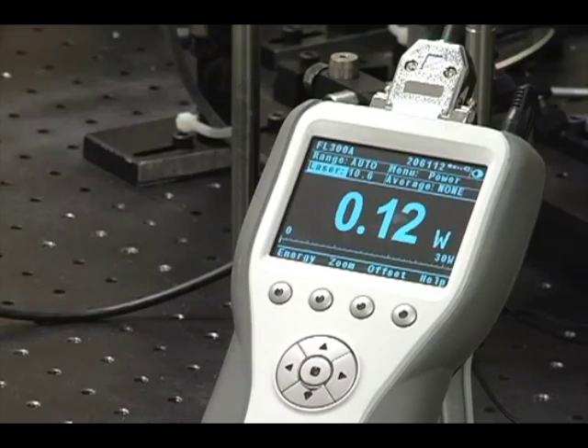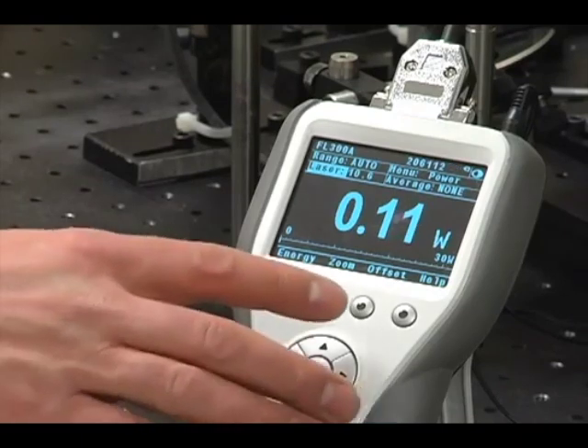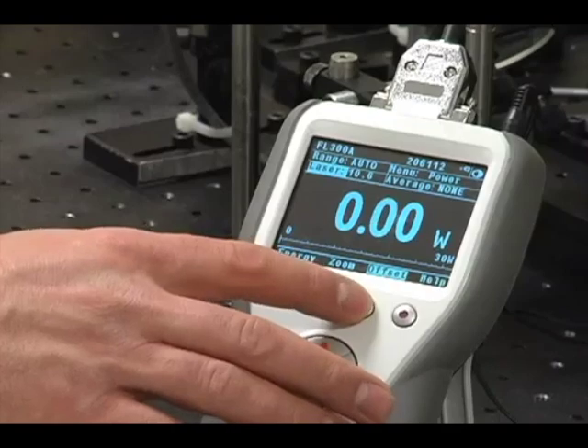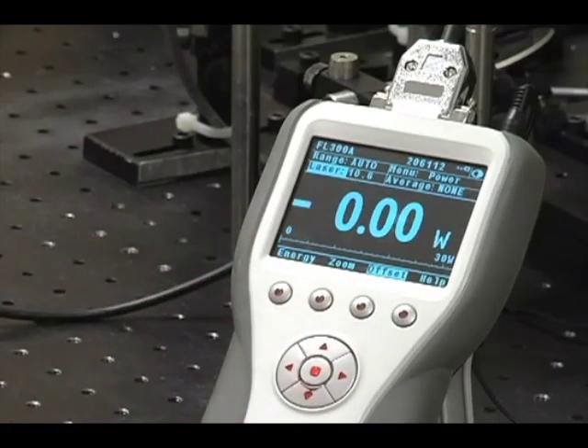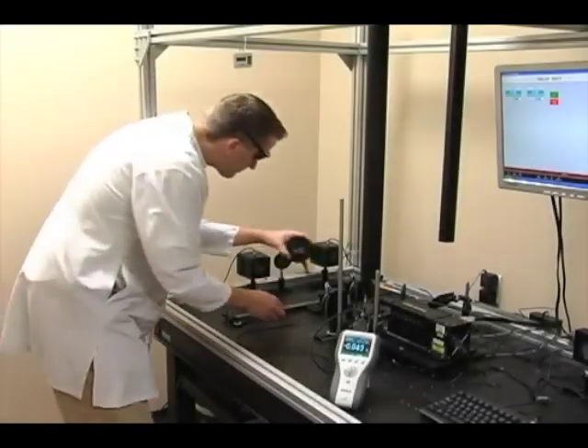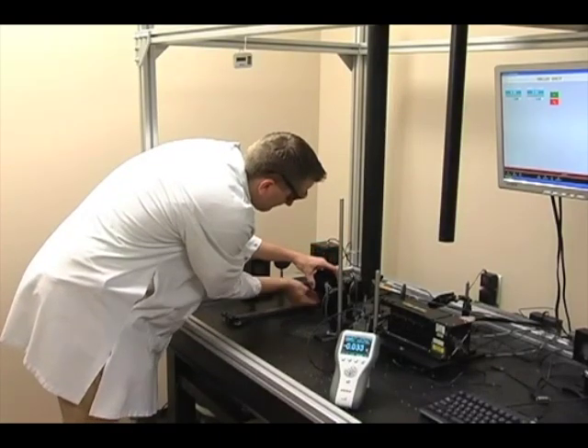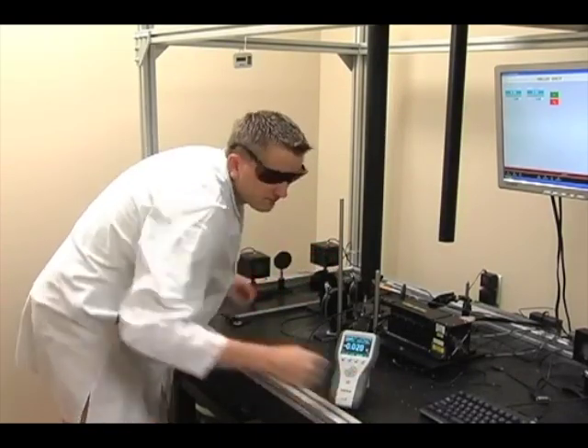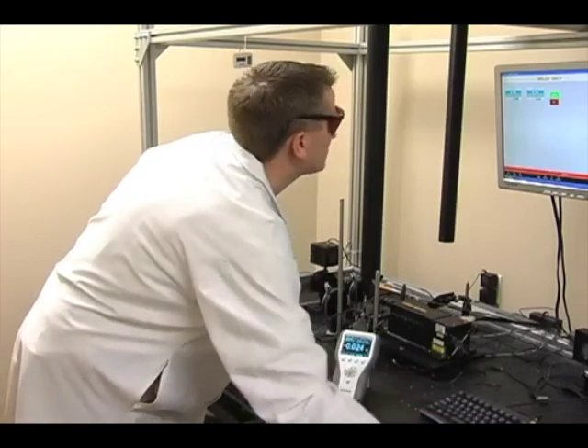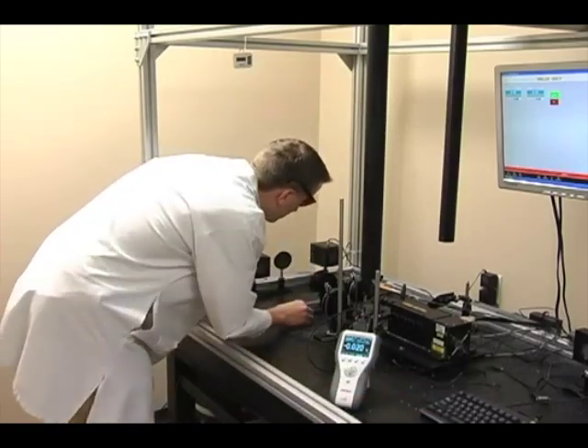Next, we'll have to zero the background ambient readings, so we'll press the offset button. Now we're all set to measure. We have the right wavelength and the right power range. Now turn on the laser on a low power and adjust the beam to be centered on the aperture.